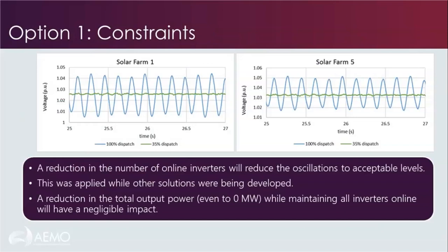Starting with option one, which is the application of operational constraints. These graphs show example responses for two solar farms with 100% of inverters available and online, and then that reduced to 35%. And as we can see very clearly here, reducing the number of online inverters to 35% would substantially mitigate the level of oscillations that would otherwise be experienced. For clarity, I've only zoomed in on the post-fault response that shows these oscillations.